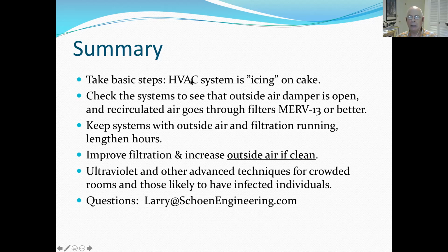If you can keep it clean and in operation, and you can get a good quality filter in there with the right MERV rating, and you can seal around the edges of the filter. I may not have emphasized that as much as I need to: if you put a high efficiency filter in, you must seal around the edges. You can use weather stripping, a foam seal, or a tight-fitting metal spring. Whatever you use, make sure there's a tight seal between the filter and the edge of the rack that it's going into. Otherwise, air bypasses around the filter, and what used to be a MERV 13 filter mixes with air that's not even filtered at all, and you get a MERV 7 filter. You don't want that.